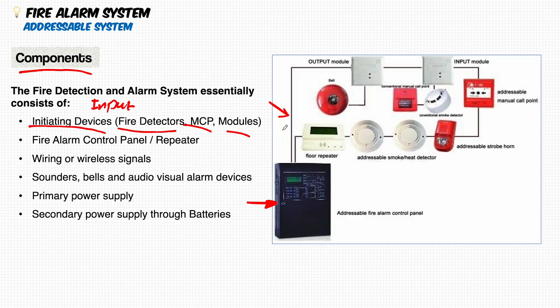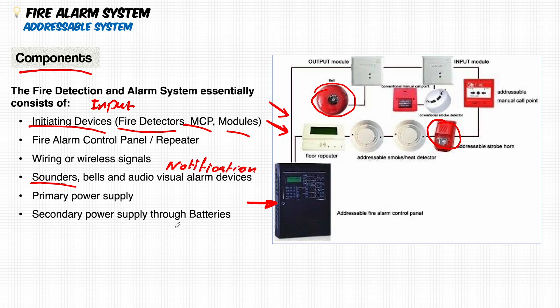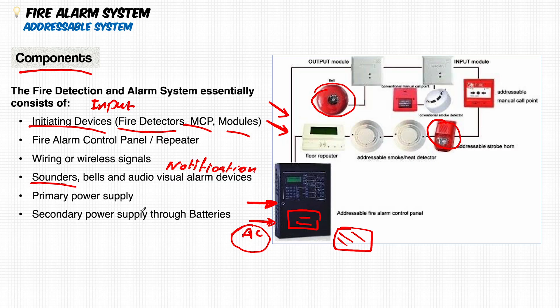The fire alarm controller receives the signal via wired or wireless connections and delivers it to notification devices. Notification devices include bell sounders, flashers, or combined audio-visual fire alarm devices. The fourth main component is the power supply — the primary source is AC current from the building, with batteries inside or outside the panel as a secondary power supply.